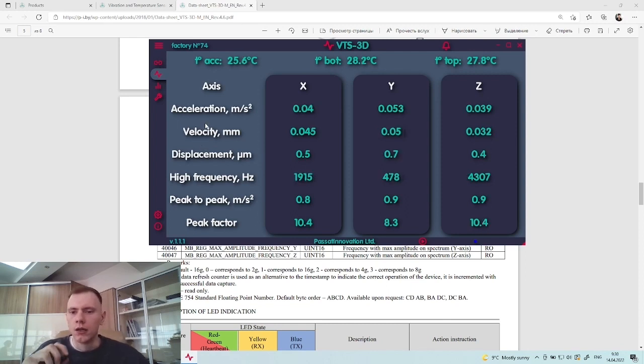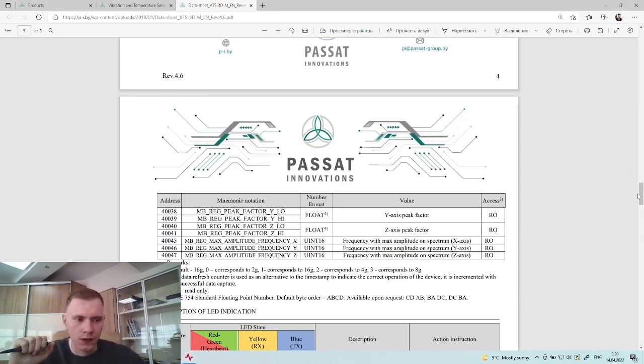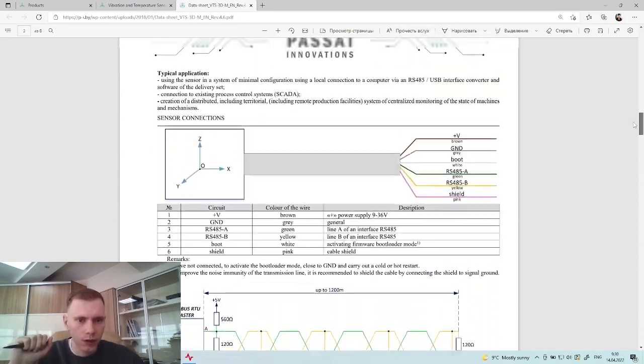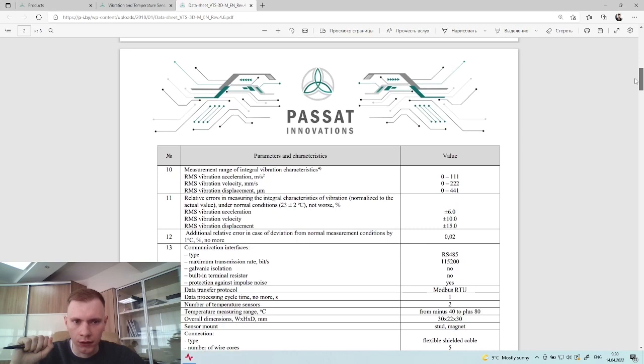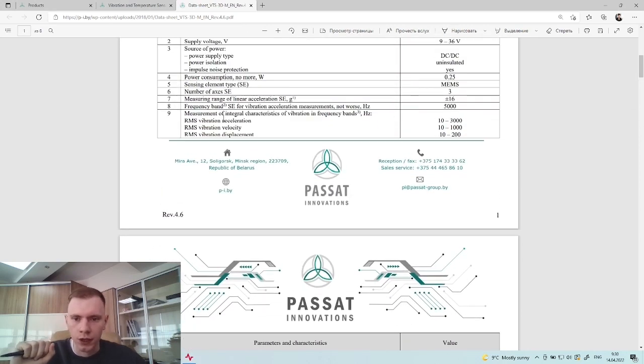So these three characteristics, acceleration, velocity, and displacement, represent the standard frequency bands, as it says in the datasheet. For acceleration from 10 to 3 kilohertz, for velocity from 10 hertz to 1 kilohertz, and for displacement from 10 to 200 hertz. What is a frequency band in our meaning?